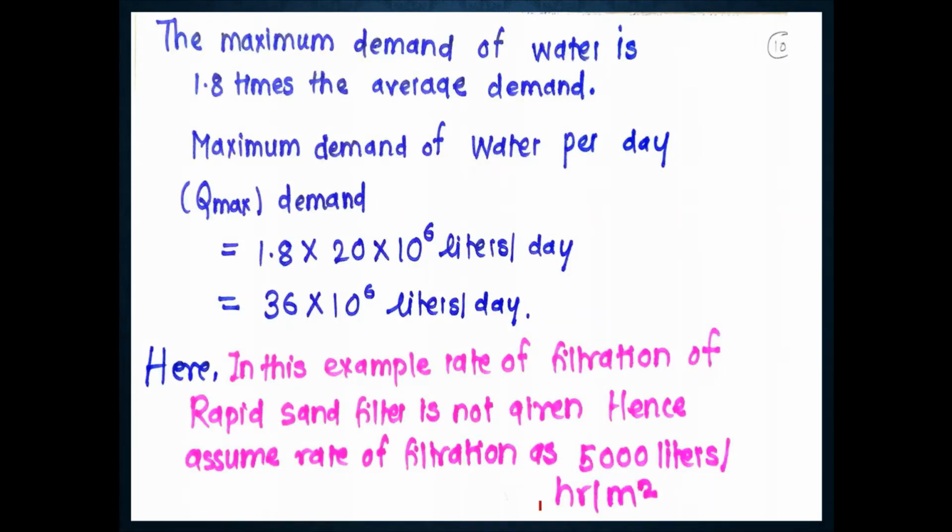Now the next assumption we will take is the maximum demand. We have not calculated the maximum demand, we have just calculated the average demand, and the maximum demand is 1.8 times the average demand.